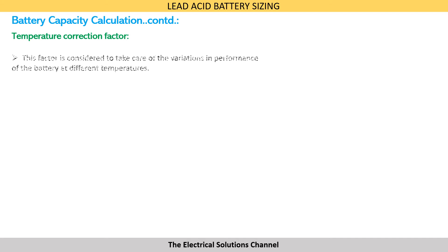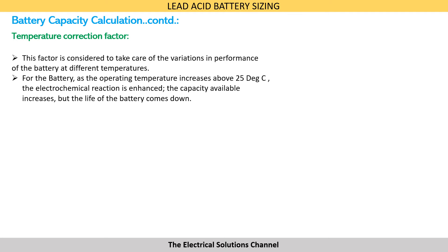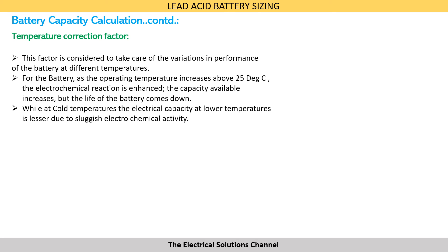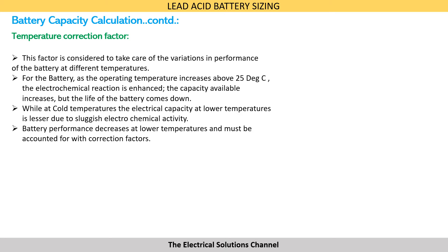Temperature correction factor: this factor is considered to take care of variations in performance of the battery at different temperatures. As the operating temperature increases above 25 degrees centigrade, the electrochemical reactions in the battery are enhanced and the capacity available increases, but the life of the battery comes down. At cold temperatures, the electrical capacity is lesser due to sluggish electrochemical activity, so battery performance decreases and this must be accounted for with correction factors.